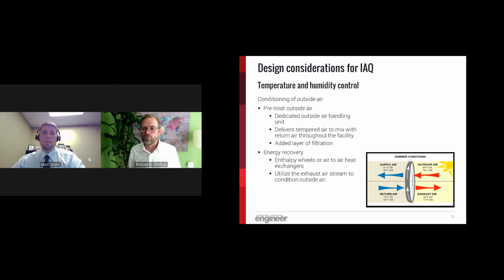In these spaces, it's common to design a dedicated outside air unit that will precondition or pre-treat the outside air before it's delivered to various air handling equipment. These units help provide a more stable airflow to be mixed with return air at the zone level air handler. And an added benefit is that these dedicated units will also require a pre-filter of their own, which is just an added layer of filtration for the overall building.